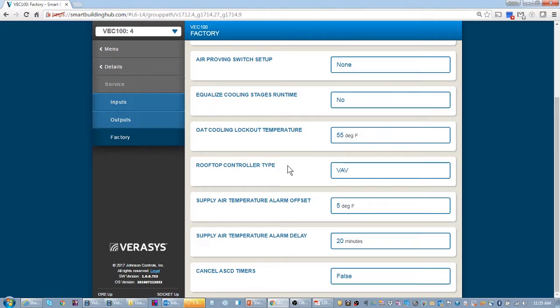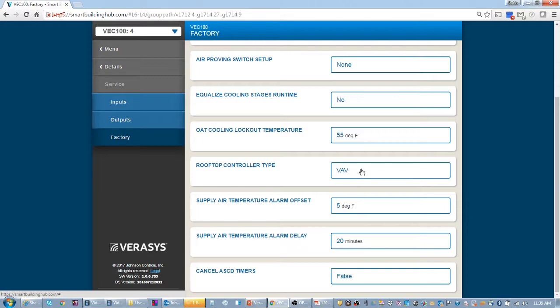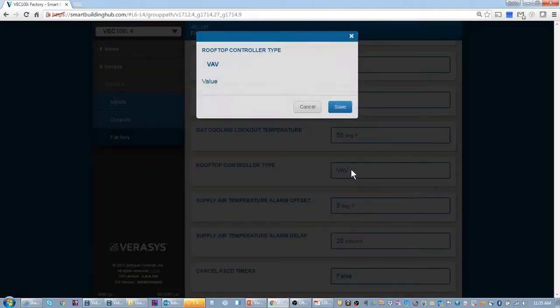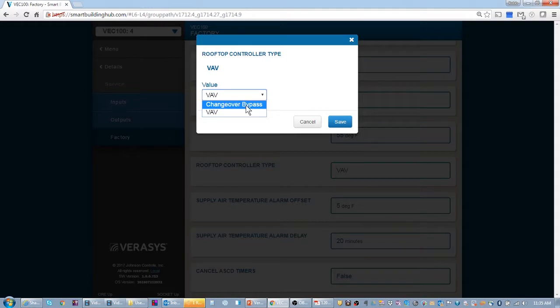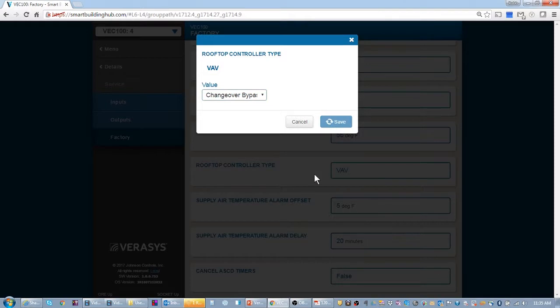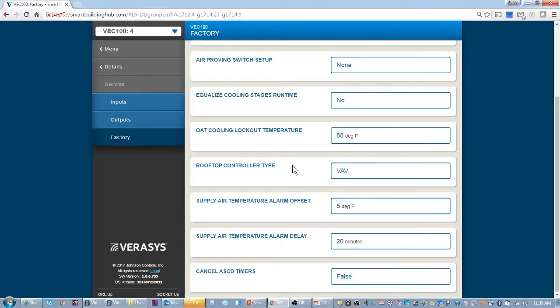I'm going to jump back to Verisys and we're going to start setting up some of these parameters. The main parameter that you have to set to say that it's a changeover bypass system is this rooftop unit controller type. As I suspected, it's set to VAV. So we're going to set it to changeover bypass.